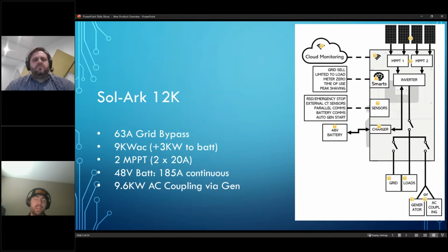That capability has been increased further in our newer products. Adding additional flexibility, we can also do 9.6 kilowatts worth of AC coupling, plus a generator input — up to 12 kilowatts of pass-through from a generator on a specific breaker built into the inverter. You don't have to piece together any more parts; you get all of that right out of the gate. A single 12K can support 120/240 split phase, 120/208 3-phase, and 220-volt single phase.